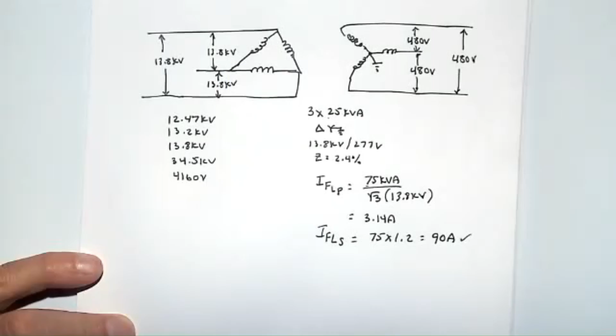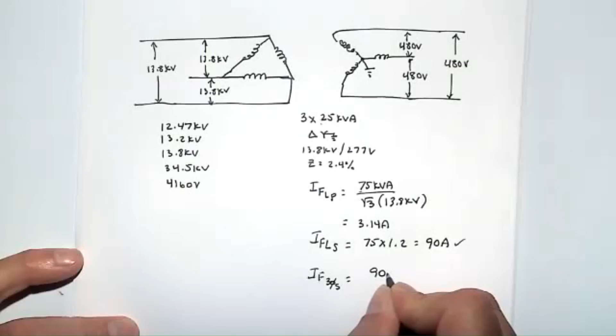Now let's calculate our fault current. So I fault 3-phase on the secondary is going to be 90 amps divided by our impedance. And again, the impedance for these guys is typically pretty small. So we're going to use the number on the nameplate in this one, 0.024 per unit, or 2.4%, and that works out to 3750 amps of fault current.